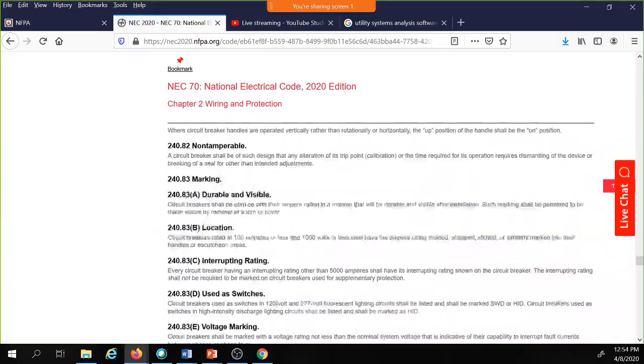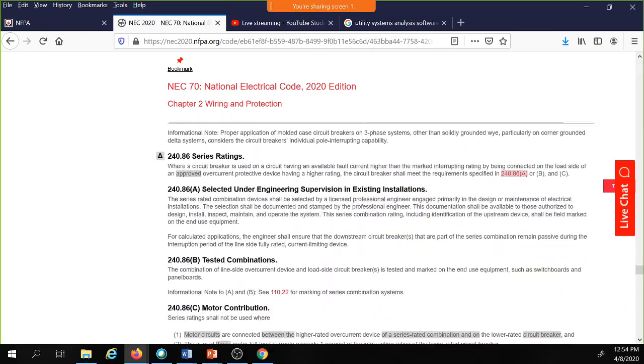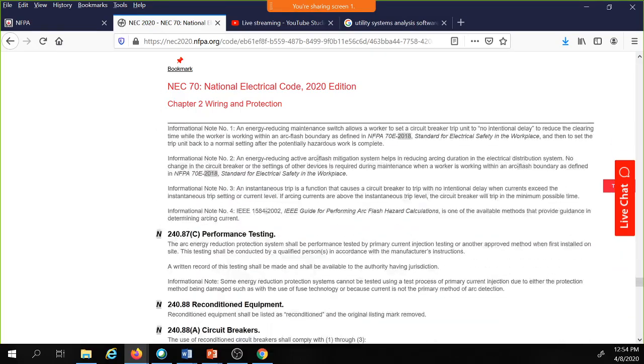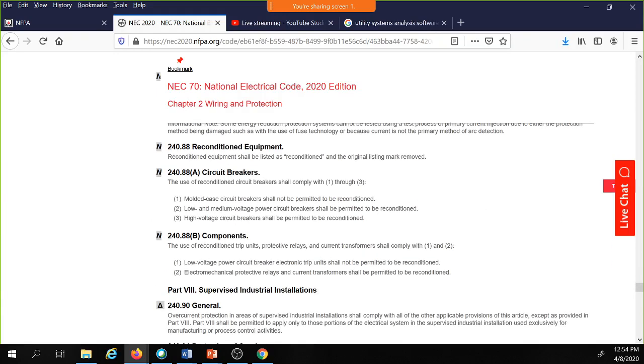Here's a key thing—I think it's 240.88, don't want to get anybody dizzy. Don't look at the screen while I scroll. 240.87, 240.88, yep. Now look what this language says: reconditioned equipment shall be listed as reconditioned and the original listing mark removed. So this is the only place in the NEC around reconditioned equipment where it says that if you recondition that breaker, it's got to be listed, or whatever that product is.